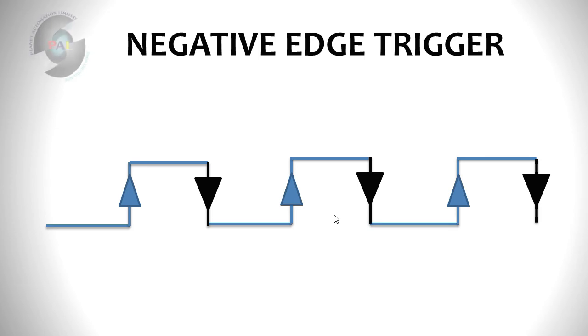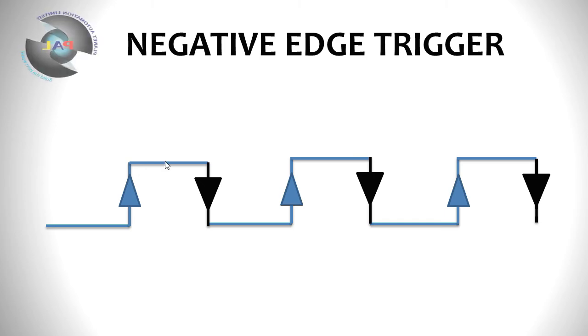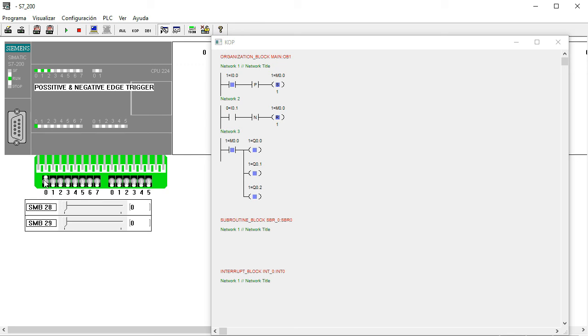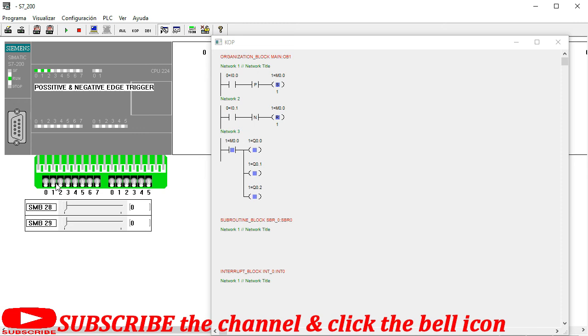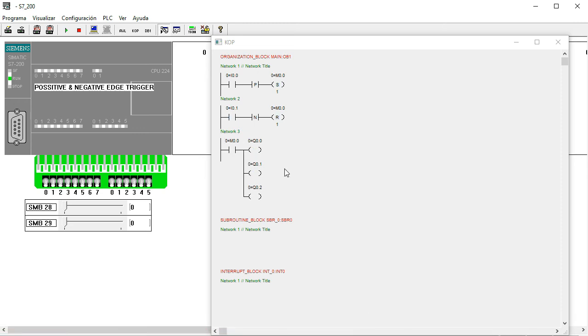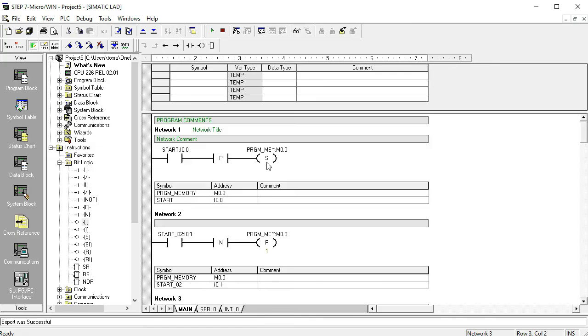I hope you understand what positive and negative edge triggering systems are. Going back to our programming sequence: the first time I0.0 is triggered, all outputs turn on — this is the working time. Then the falling edge command turns everything off. So we control our outputs with one pulse: the positive edge turns outputs on and the negative edge turns them off.